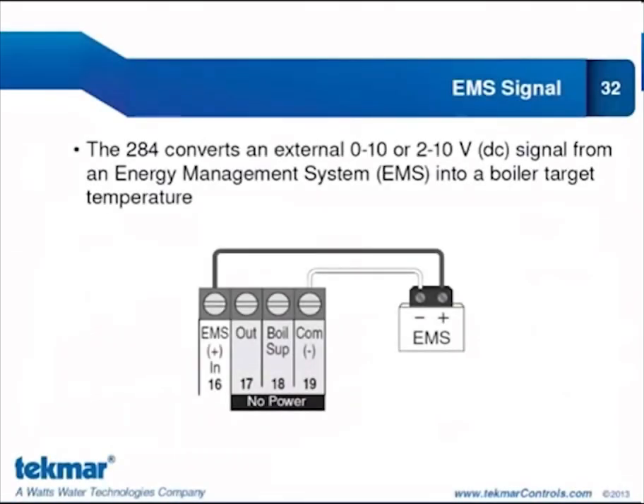By selecting application mode EMS, the 284 converts an external 0 to 10V or 2 to 10V signal from an energy management system into a boiler target temperature. New on the 284 are dedicated terminals for the EMS input — we're no longer sharing that with the outdoor sensor terminals. This is one-way communication: the 284 receives a water temperature from the EMS but does not communicate anything back. To clarify terminology: EMS refers to the input received from an energy management system, while EMS1 and EMS2 are outputs used to control boilers requiring a temperature-based target.